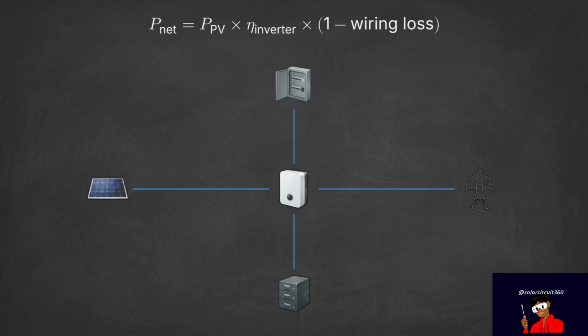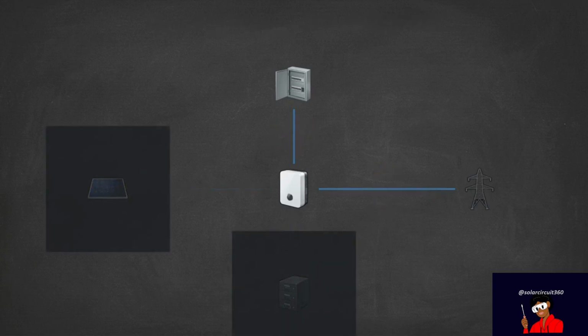Real-world net power subtracts both physical wiring losses and the inverter's internal efficiency drop. Converting direct current from the panels into alternating current inherently bleeds power off as heat dissipation. Physical DC wiring runs cause voltage drop due to resistance, shedding energy before reaching the inverter. The inverter executes an automatic arbitration hierarchy, prioritizing solar power to the load, then charging the battery, and finally feeding the grid. This entire arbitration sequence is rigidly restricted by the system's rated maximum currents.